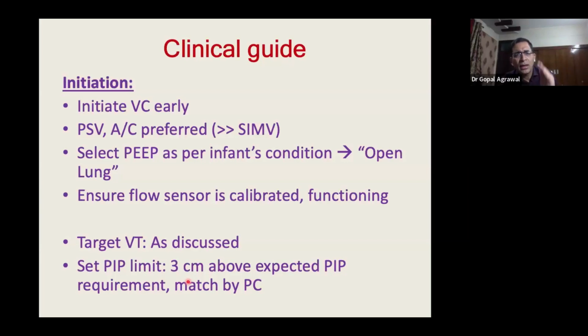So when you start off with ventilation in volume guarantee, you set a PEEP as per baby's condition, ensure that the flow sensor is working, choose assist control mode of ventilation and volume guarantee, set a tidal volume, and set a PIP limit. You cannot set PIP here. PIP will be variable, but you'll need to set a limit which should be at least 5 centimeter above the expected PIP requirement.